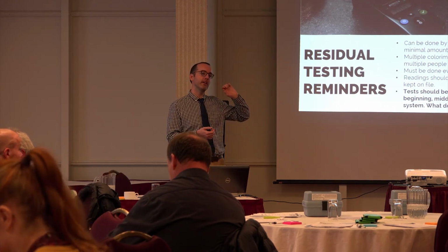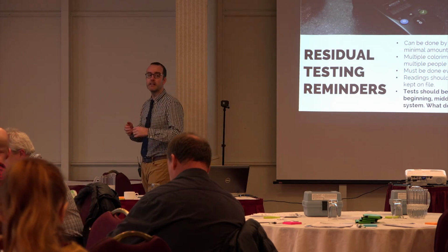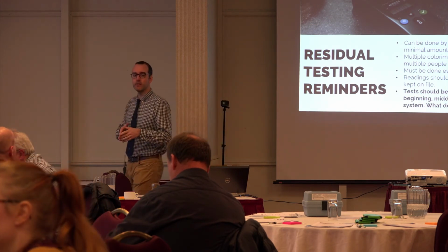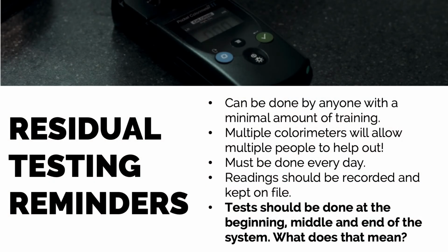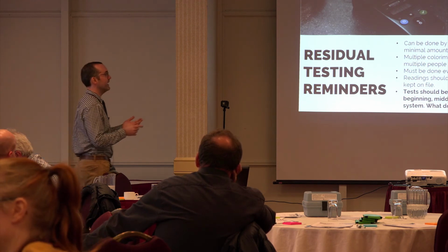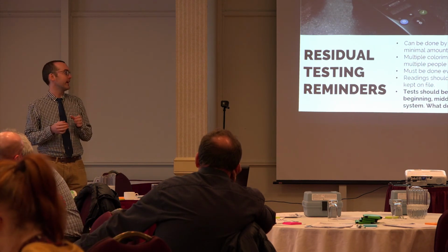Some people rely on just taking measurements at their point of disinfection, say inside their pump house. An operator who just goes there never goes out into the field with his handheld unit, never takes those samples out there. To get off a boil water advisory, if you're a community that's on a boil water advisory and you want to lift it, you're going to have to prove to an EHO and anyone else involved that you're getting the right amount of disinfection in the beginning. You took your measurement, okay, the right amount of chlorine is being added, and you've gone out to your system to find out that chlorine stays in that system. And you've got to have a test in the beginning, the first user, tests out in the middle to see how the system's behaving, and at the end.